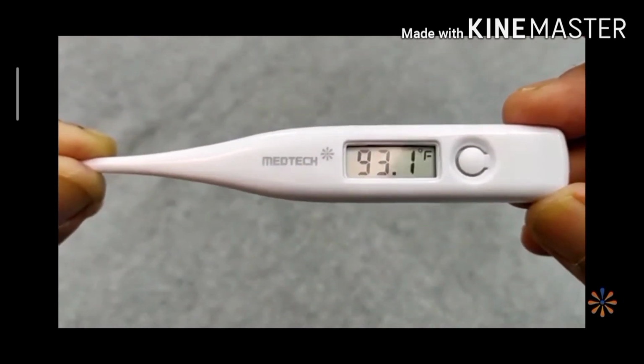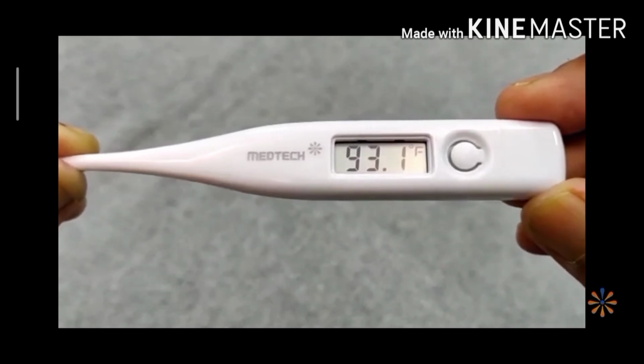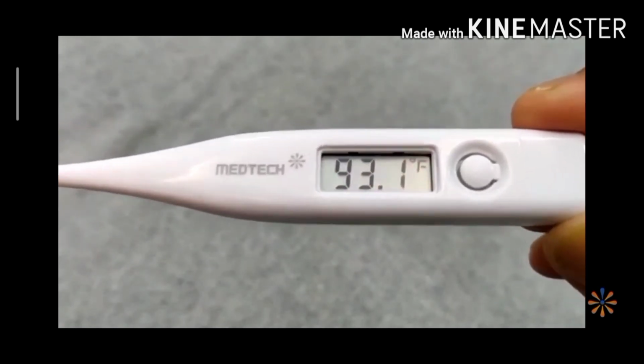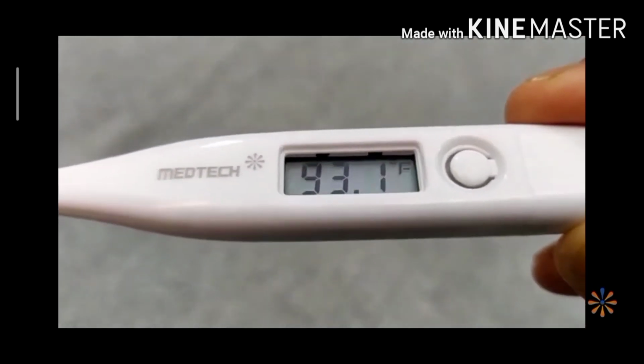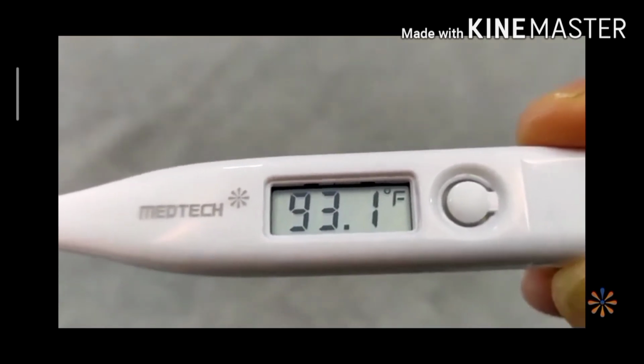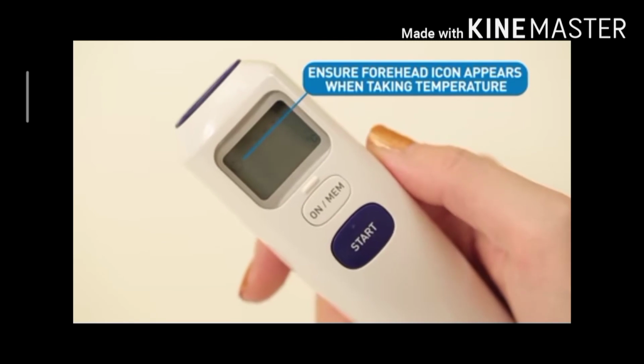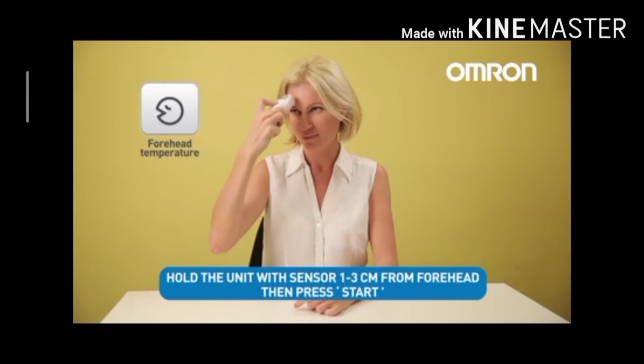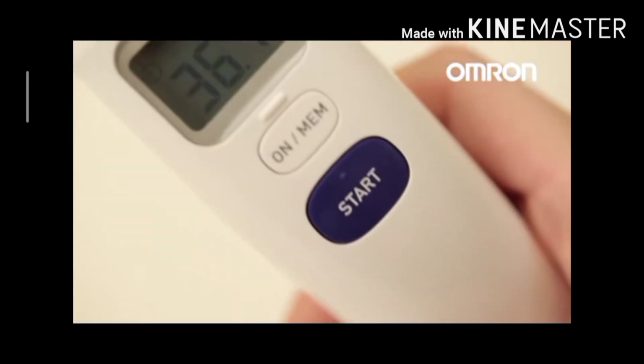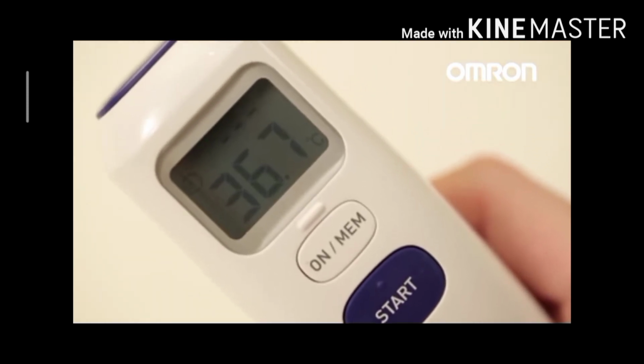The reading is stable here. That means the body temperature of that person is 93.1 degrees Fahrenheit. So it is very easy to measure the body temperature by using the digital thermometer. In these corona days, we are observing the forehead thermometer, which measures the body temperature within seconds. Hold the thermometer near the forehead, then press start. Then we get the body temperature within seconds.